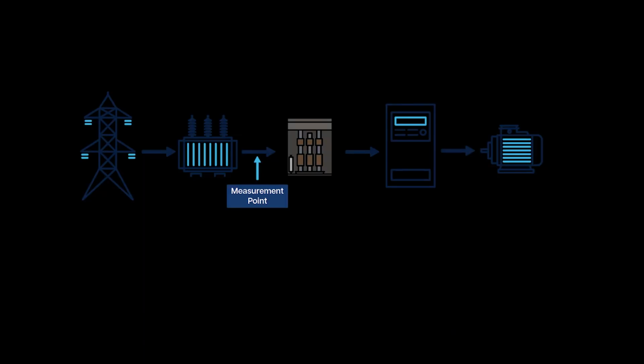The passive harmonic filter is designed to integrate in line with these sources, again, namely a variable frequency drive. By mitigating the harmonics, we're going to be able to meet a specification commonly referred to as IEEE 519. Essentially, what that's going to do for your facility is we'll be able to take that circuit that might have 30 or 40% or more of harmonic distortion content, and mitigate that down to below 8% or even below 5% to meet the IEEE 519 requirements.